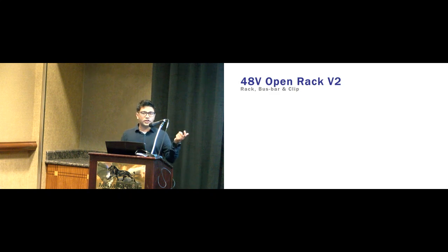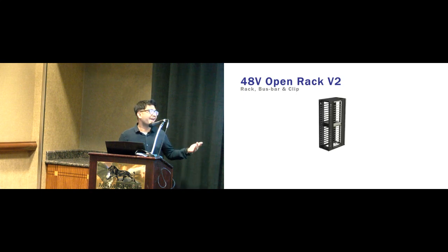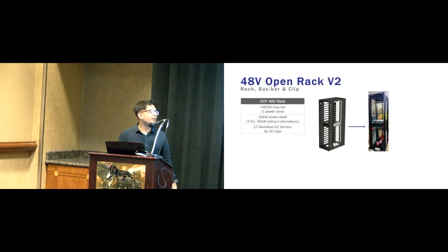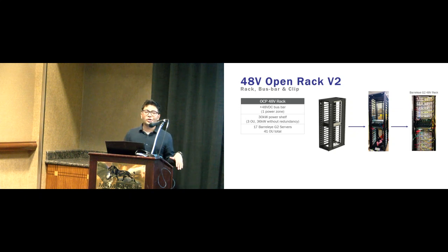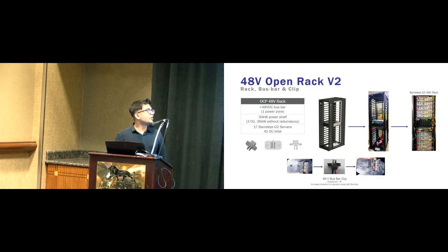So you have server, you have I/O, you have a power shelf. You need a rack, so we built a rack. We integrated the power shelf, loaded it with all the systems, and tested that. I like to abstract away the detail, but just for fun, even to get this 48 volt Open Rack clip, we had to go through multiple revisions and get the alignment between the clip and the bus bar right. The devil is in the details, but it's up and running, and things are working. So that's exciting, right?